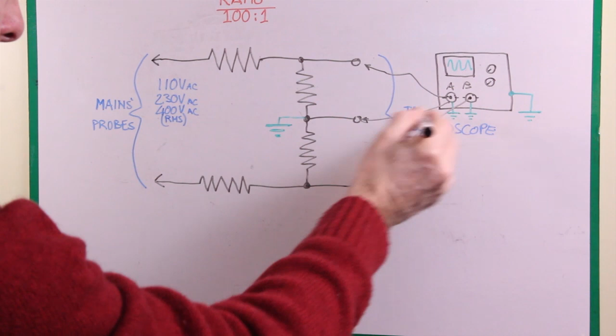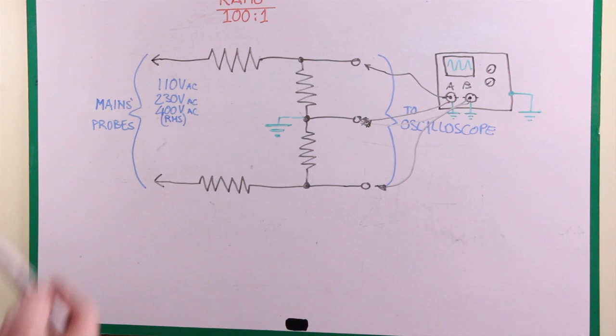And of course, the ring here is connected here, and this ring is connected here to this point that is tied to ground. First off, we have to prevent the risk that the RCD could trip because of the current that flows through this branch and this branch toward ground. This is pretty easy to solve.